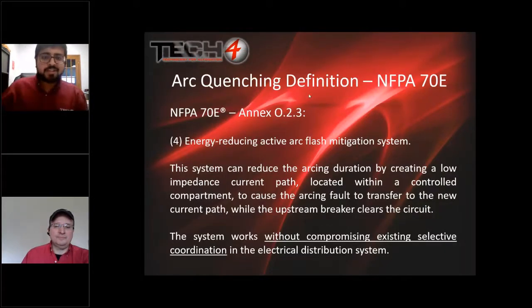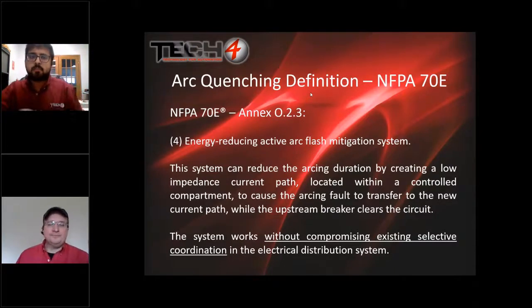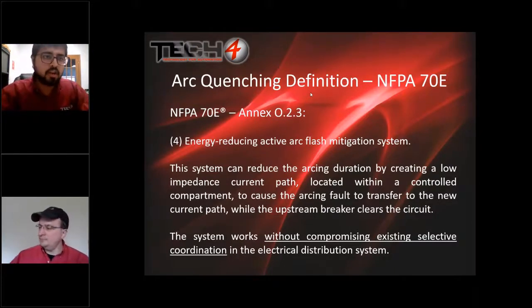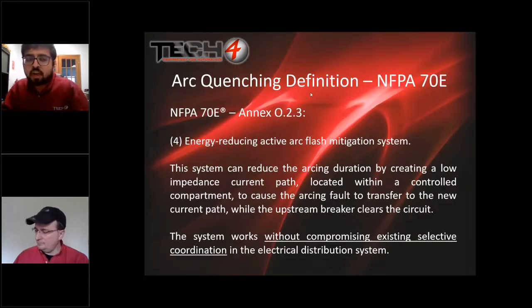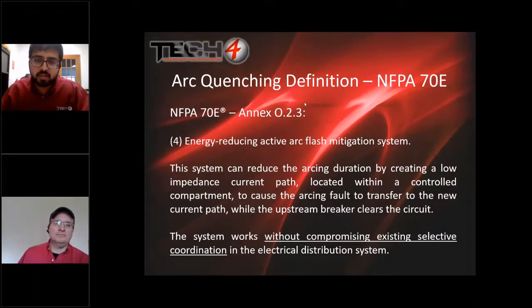So this is just a slide of what the arc quenching definition is. The system can reduce the arcing or extinguish the arc by creating a low impedance path. And in this case, in our system, it shorts all the 3 phases, and the collapsing of the voltage extinguishes the arc.